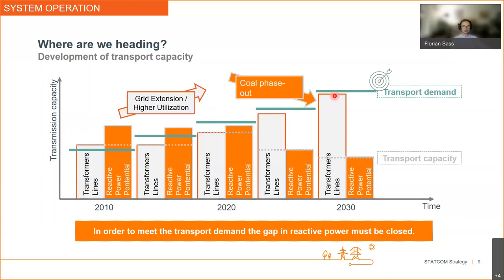But the coal phase out hit us. Reactive power potentials are decreasing. And suddenly, the reactive power provision is the limiting factor regarding transport capacity, meaning we can't provide the consumed reactive power of the system anymore.